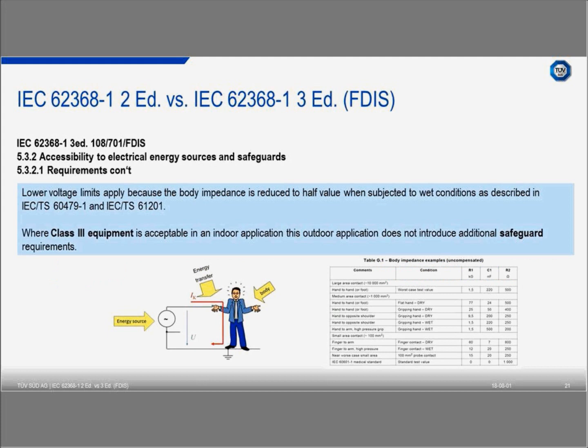So the topic is, why do we have this - let me give you information here. There are two standards or technical specifications, 60479-1 and also technical specification 61201. There's a table there: we have to consider that for outdoor equipment, instead of the dry condition we normally have with our product, we have a wet condition, and in this wet condition the body resistance will be lower. This is the reason we have to reduce the voltage for ES1 by 0.5.